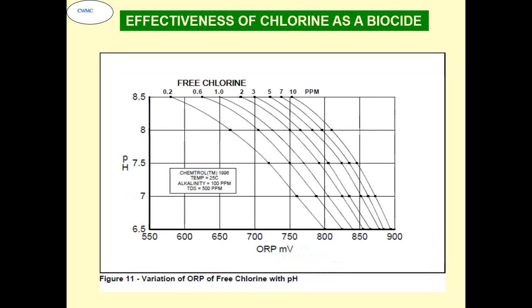Okay. If we look at it, there is a correlation with the ORP, which is oxidation reduction potential, the potential which is generated when the system is in equilibrium. So there is an oxidizing reaction, and there is a reduction reaction. That ORP measurement is a tool which can give you a direct indication of the effectiveness of the biocide. Even if you are maintaining 0.2 ppm free residual chlorine, and the system is effectively working, you will get more than 550 millivolt ORP. In a very good condition, you can get even up to 800 millivolt, but at least around 550 to 600 is a normal thing that you can expect in a good clean system.